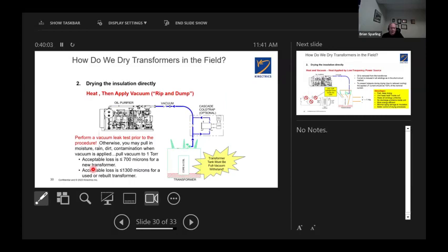And conventionally, what we've been doing for years, some people call it rip and dump. You apply heat to the oil in the transformer. You circulate it through the oil processing unit. You circulate it, inducing heat from the outside through the oil and trying to heat up the windings and the solid insulation by inducing hotter oil, not real hot oil. And then suck the oil out. And as you're circulating it, you're trying to suck the moisture out of the oil.